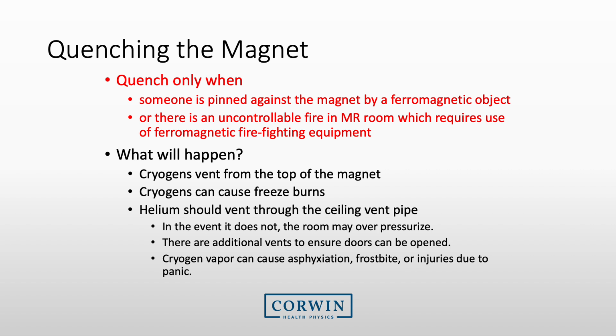If you do hit the button, cryogens will vent from the top of the magnet. These cryogens can cause freeze burns. If the gases do not vent, the room may overpressurize. There are typically backup vents to ensure doors can open. This cryogen vapor can cause asphyxiation, frostbite, or other injuries.